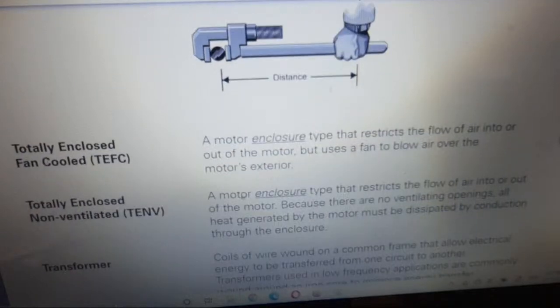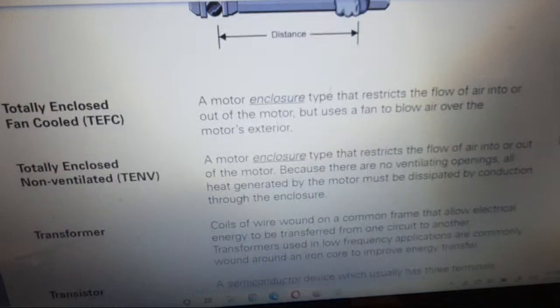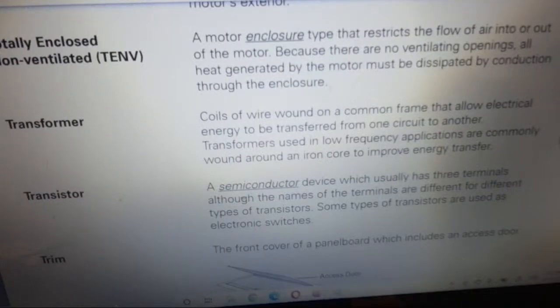Totally enclosed fan cooled, TEFC, a motor enclosure type that restricts the flow of air into and out of the motor, but uses a fan to blow air over the motor exterior. Totally enclosed non-ventilated, TENV, a motor enclosure type that restricts the flow of air into and out of the motor because there are no ventilating openings. All heat generated by the motor must be dissipated by conduction through the enclosure.